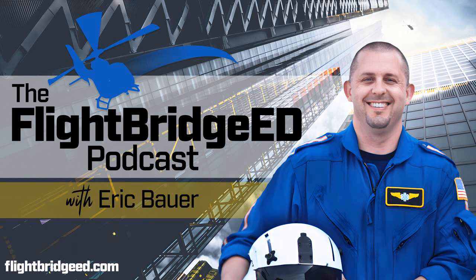It takes a little bit more expertise. It takes a little bit more thought. You're going to have to be watching your patients a little bit more closely. So how do we set this up? We're going to set our respiratory rate, and we're going to set our inspiratory pressure. The inspiratory pressure is going to give you a tidal volume. All right, so your tidal volume button in this mode of ventilation is not going to work. It's going to be probably whited out. It won't light up, and so you're going to set the tidal volume off of this pressure.